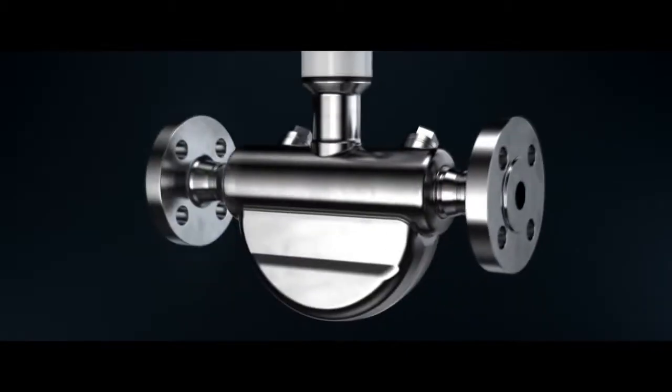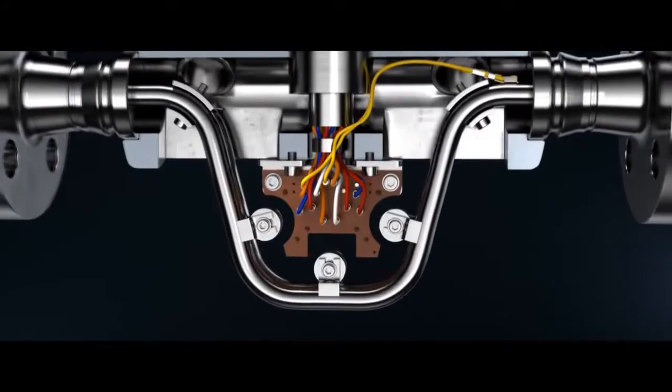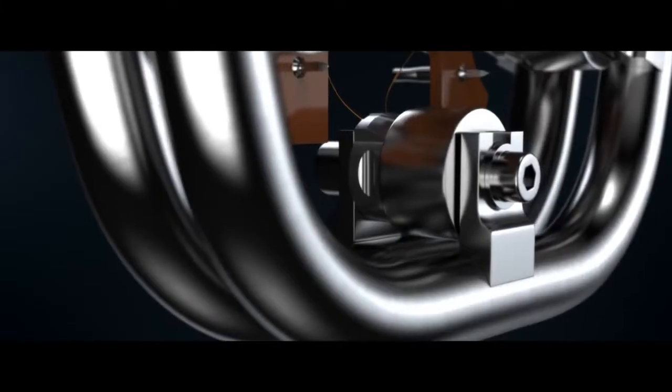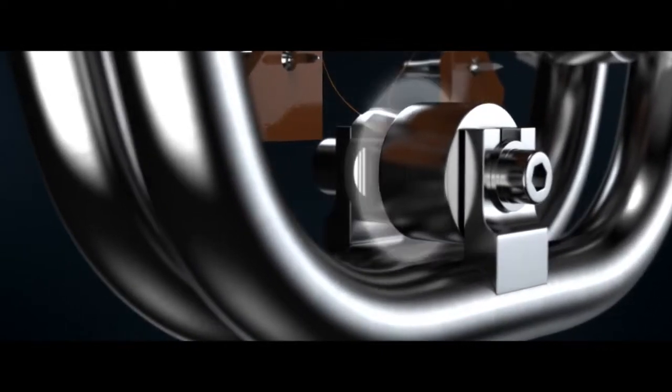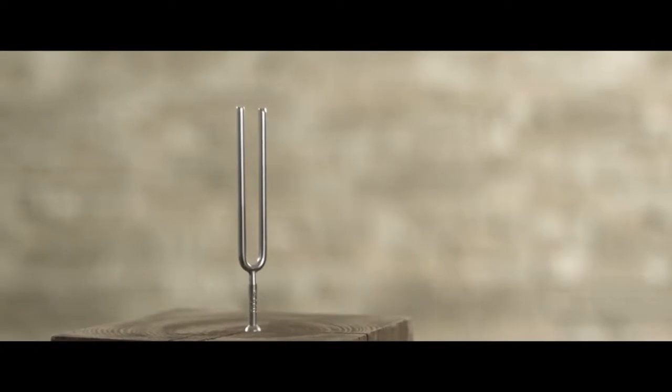The Siemens SITRANS FC430 flow meter functions according to the same principle. Two symmetric metal tubes are set vibrating. This is ensured by a driver coil in the central section. The tubes oscillate with a resonance frequency, similarly to a tuning fork.